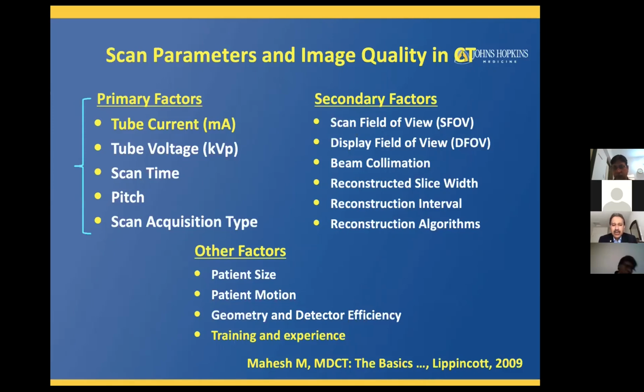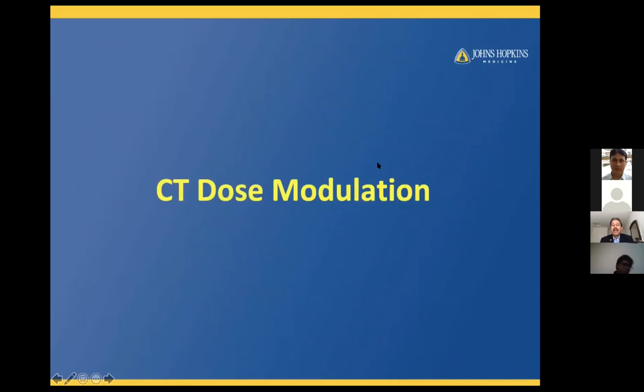The patient dose varies directly with tube current. With respect to tube voltage, the patient dose varies as kV squared. And the scan time, pitch, and acquisition time, especially the scan acquisition type, are important when we are doing a cardiac CT. The secondary factors impact the image quality, but not the dose directly, because it's already acquired data. So let me talk about CT dose modulation.